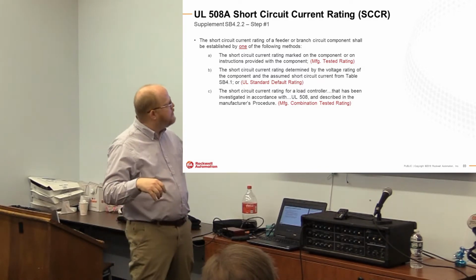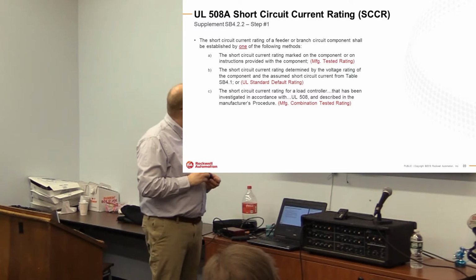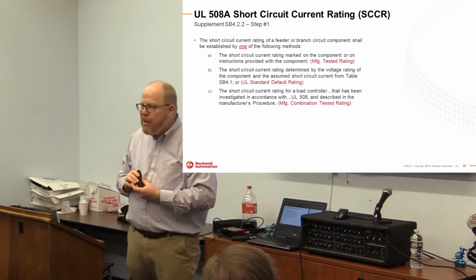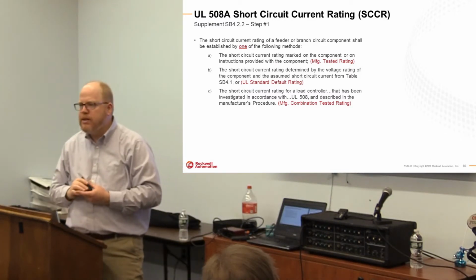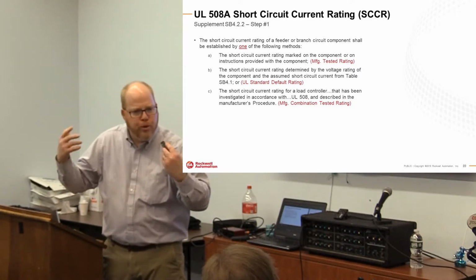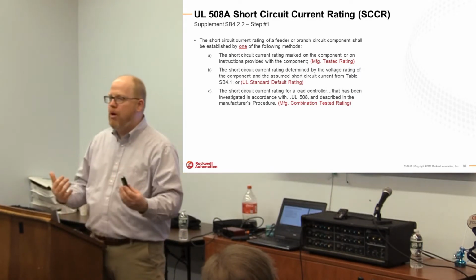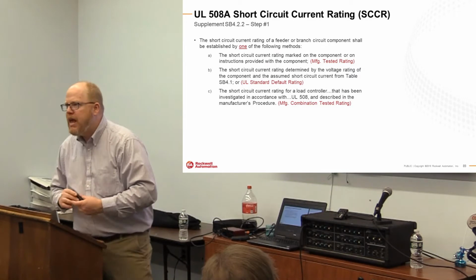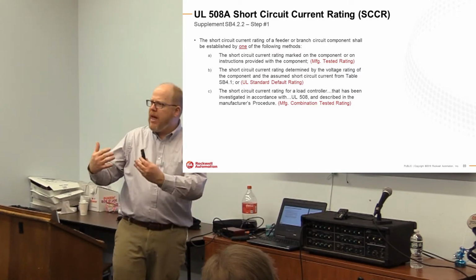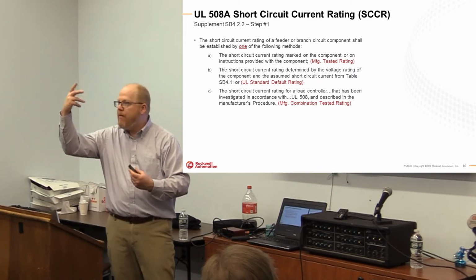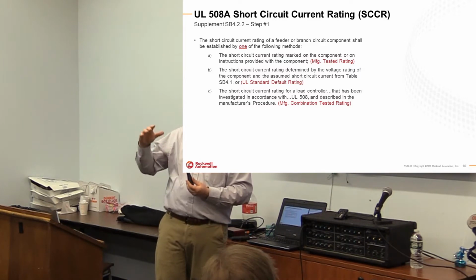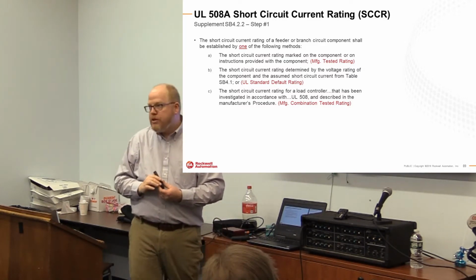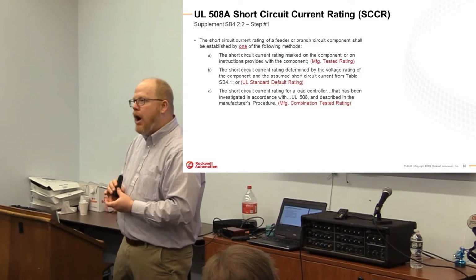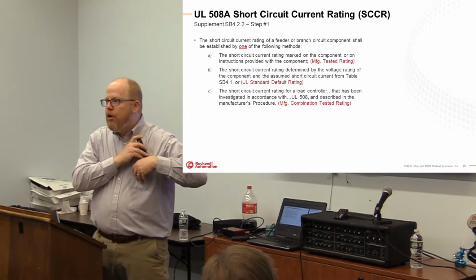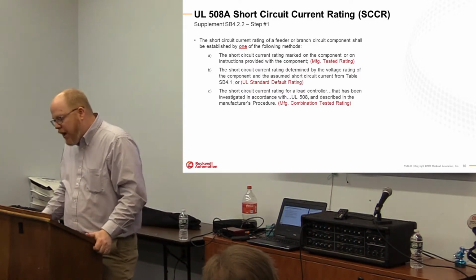Now, you could also grab data from what's called the UL standard default ratings, or there's a table in SB4, which you'll see in another slide, that has pre-canned ratings for typical components. Again, usually fairly on the conservative side, but that is another source of data if you don't have the manufacturer data for the component.